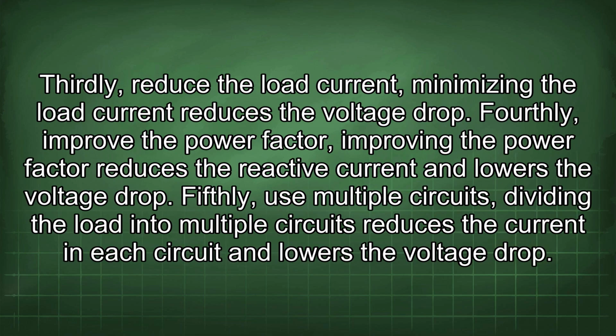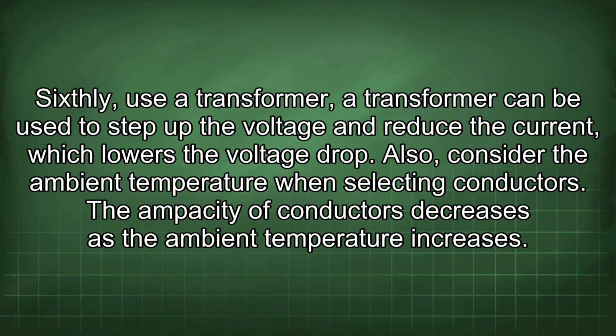Thirdly, reduce the load current. Minimizing the load current reduces the voltage drop. Fourthly, improve the power factor. Improving the power factor reduces the reactive current and lowers the voltage drop. Fifthly, use multiple circuits. Dividing the load into multiple circuits reduces the current in each circuit and lowers the voltage drop. Sixthly, use a transformer. A transformer can be used to step up the voltage and reduce the current, which lowers the voltage drop.